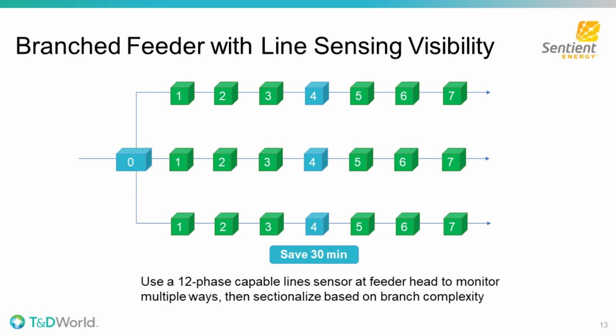And the next step would be, like we did on the feeder, to add visibility at the midpoints. And here we see visibility with 3-phase line sensors in cabinet 4 on each feeder branch. So on a branch circuit with 4 sensor locations, and one of those is 12-phase, 3 of them are 3-phase, we can save the crew 30 minutes when finding faults.